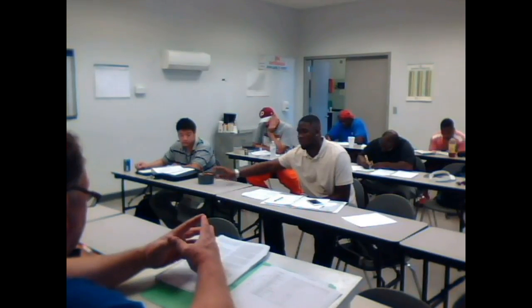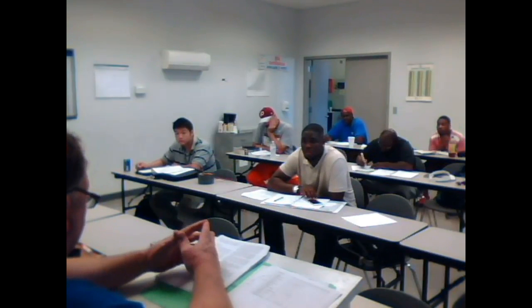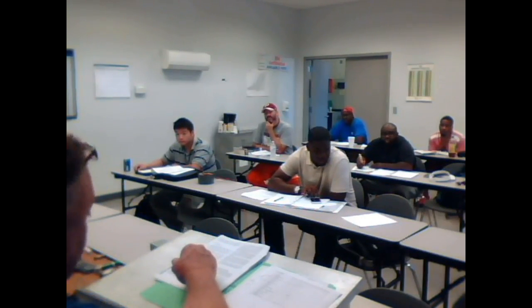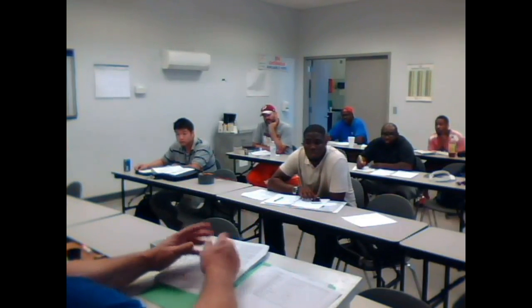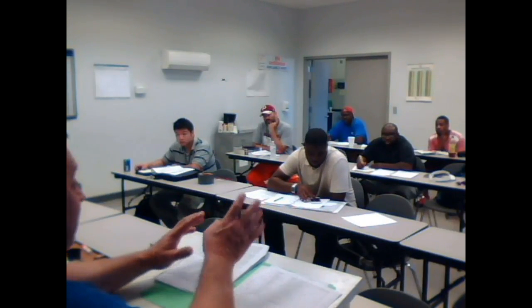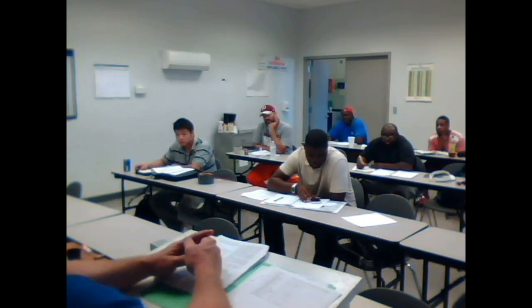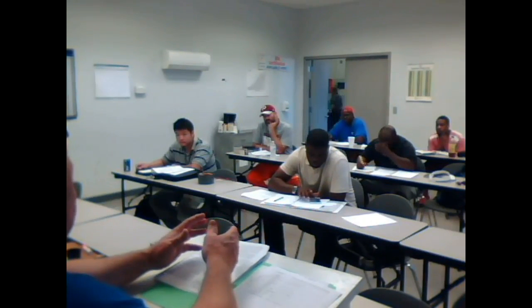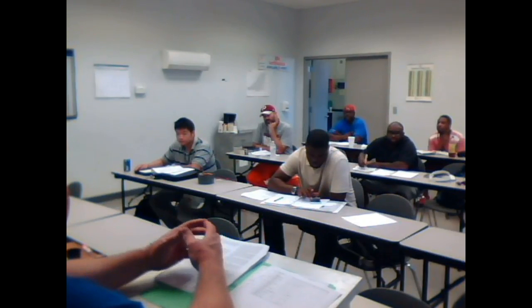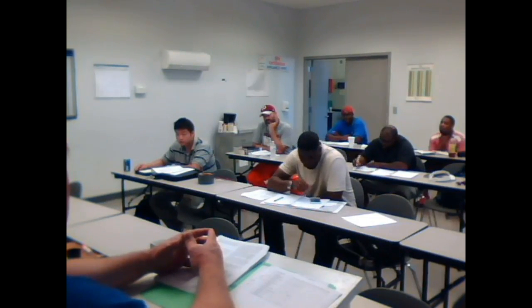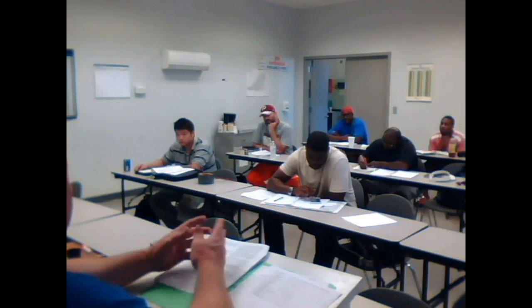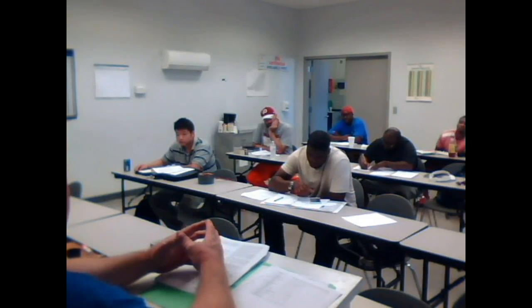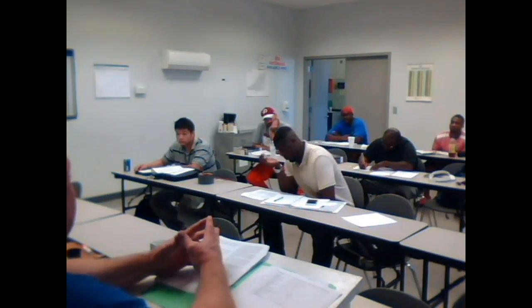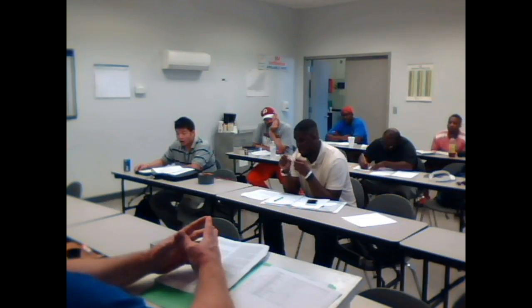Alright, so when you get to the customer's house, if it's above the 10% range, I would recommend probably going to their breaker box and checking the power coming in, because if it's high on your air conditioning circuit, it's probably high on everything. Okay, this is the problem. Like we said, if we've got higher voltage, means I got higher amperage. We look at the formula. Higher amperage means more heat. Everything's breaking down earlier. Nothing we can do about it, but you need to tell the customer they need to contact their, either Alabama Power or whoever they're buying their power from.